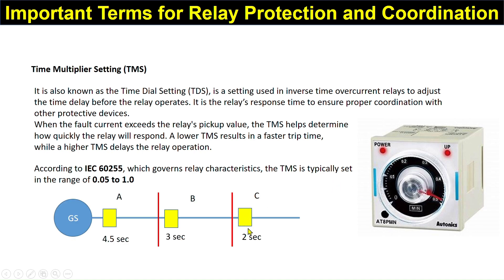This simple diagram shows a radial system. If a fault occurs in zone C, this relay will respond in 2 seconds. If that relay fails to respond, the next relay will wait and respond within 3 seconds. If that relay also fails, the upstream relay will operate in 4.5 seconds. In this way, the relays maintain coordination.